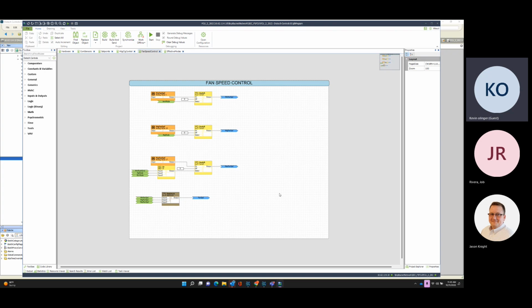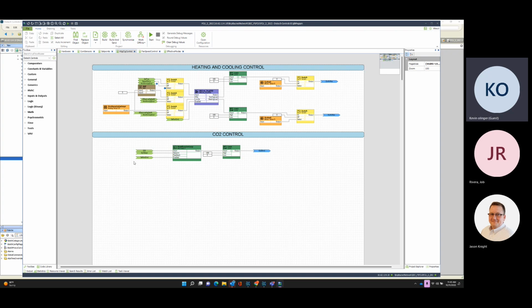If one motor is not doing work, does the status go off? Does it take both ECMs to be true to make the status true, or does either one true make the status true? From what we're seeing, it takes both to make the status true. Okay, perfect. That's helpful for us. So at least we still have a mechanical flag.